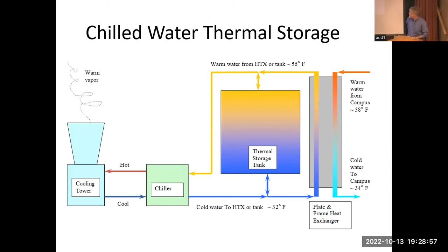Next slide, Ernie. This is our thermal storage tank at the university. It's about 2.5 million gallons, 80 feet across. It looks like it's 50 feet high, but it goes another 20 feet into the ground. The water inside it, when we cool it off, is about 31 degrees Fahrenheit. There's a little bit of nitrate, so it doesn't freeze even until it gets about 25 Fahrenheit, below our normal freezing temperature. I look at this as an ATM, an automatic teller machine.